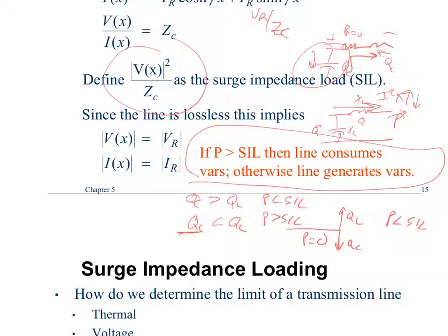So at night, you end up generating more VARs in your system because the power demand of the line is less than the surge impedance load. During the day, it's the exact opposite. Which one is harder or more challenging, or which one is a concern at all? Maybe that's a better way. Are you concerned at night or during the day or both?